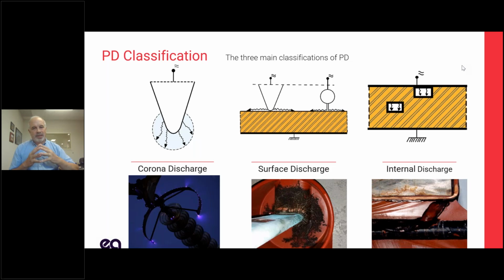The next form, and by far the most common, is surface discharge. Surface discharge is where this current is going across the surface of the insulator, and that tends to damage the insulator. It tends to create a lot of side effects. It leaves that black carbon tracking shown in the picture below there, and a variety of other effects that do things like cause the copper to turn green. You can see in this picture the copper's turned green. So this is very common, it's the easiest to find, but it's also the fastest moving and most destructive.